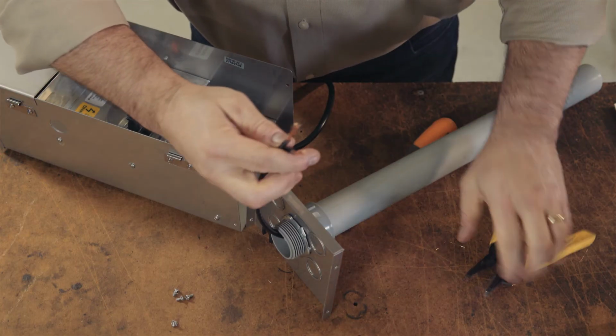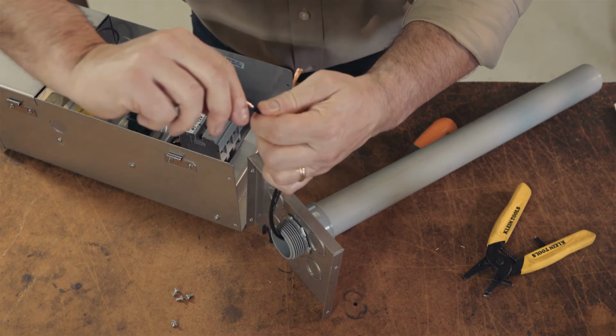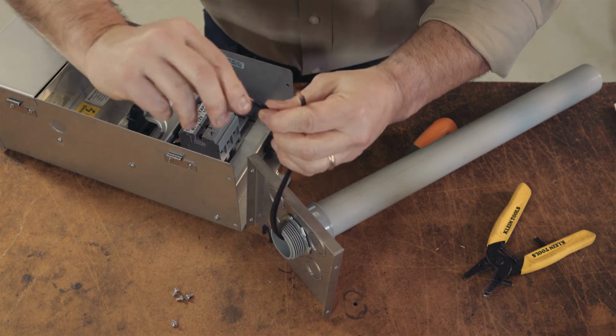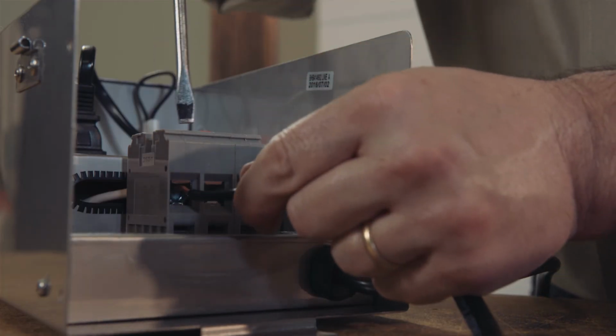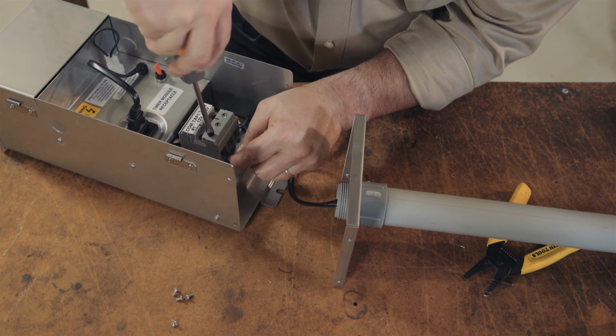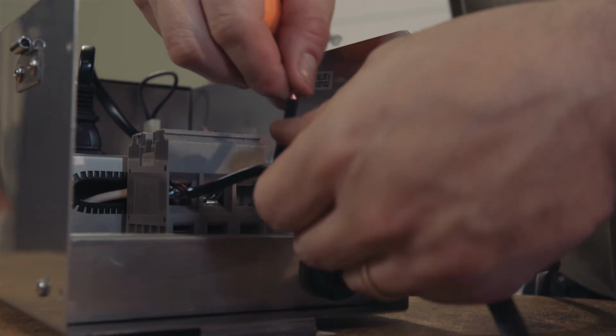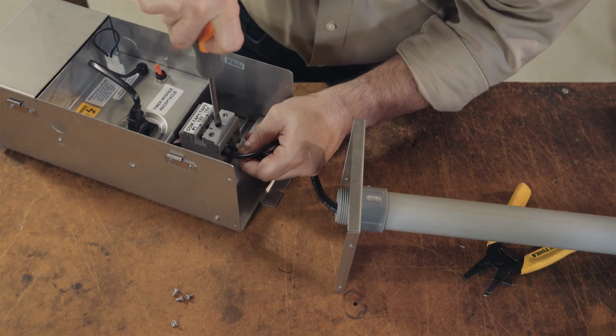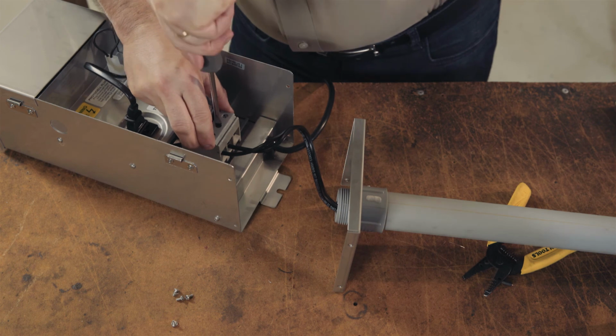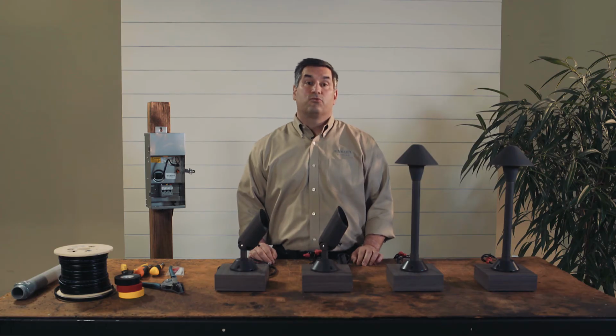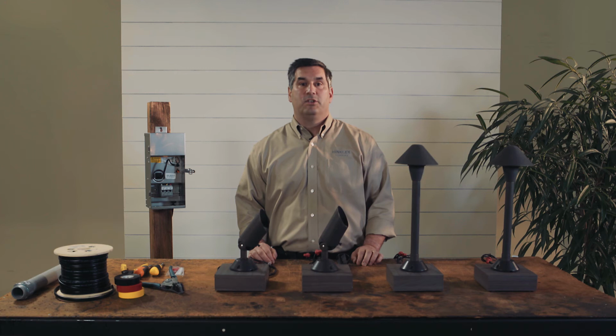Again, strip the wire back about 3/4 of an inch and place one side into the common and the other side into the 12-volt tap. Use a flathead screwdriver to tighten each tap down. If you have a longer run, over roughly 100 feet, we recommend you use the 15-volt tap to assure the right voltage to the fixtures. Remember, the driver technology built into each and every fixture will regulate what the LED will need to operate as long as the voltage at the fixture falls within the 10 to 15 volt range.